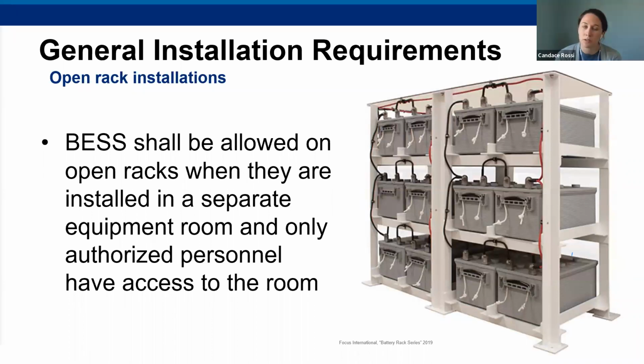Here, I think something you would see more for lead acid batteries and isn't really prevalent when it comes to lithium ion, is where systems are installed in a separate equipment room and only authorized personnel have access to the room, and they shall be permitted to be installed on an open rack. This is a common theme: you want to make sure that all these systems are secure from unauthorized access, as they can pose hazards. So if someone is proposing that open rack installation, once again, they need to be installed in a separate equipment room and only authorized personnel have access to them.